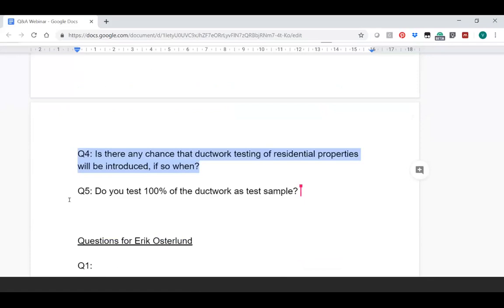Okay, thank you, so I guess this is a no. And do you test 100% of the ductwork as a test sample? Yes, you test 100% of the ductwork for low pressure ductwork, because that's relatively easy to get the results. If someone is requesting a high pressure system, as I said earlier, they may select a random area for testing. But otherwise, as requested in the specification, if the ductwork requests testing to Class A, then all of that Class A system must be tested.